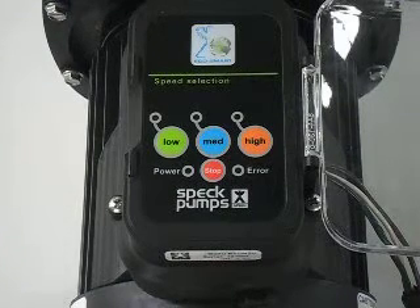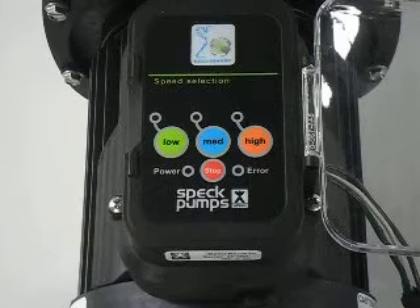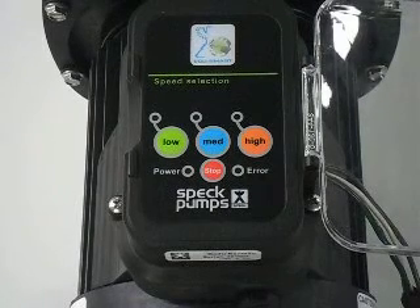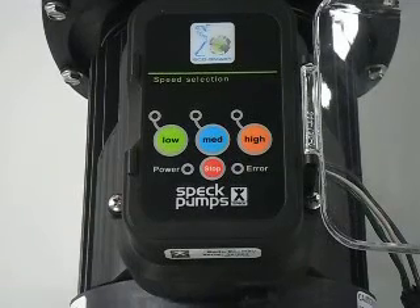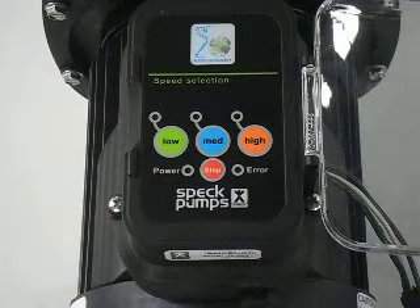Speck Pumps instructional video: Badu EQM3V variable speed pump. It comes from the factory with a default speed of low. In order to change this, the pump should be fully primed after installation, and then the power cut for a full 30 seconds.